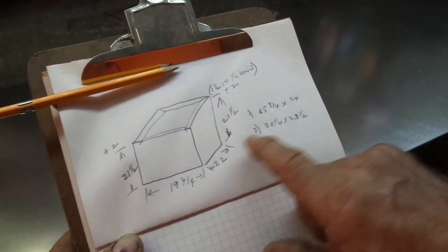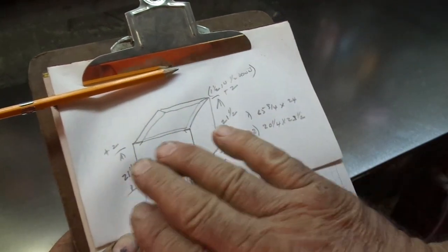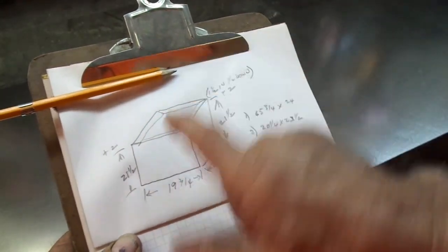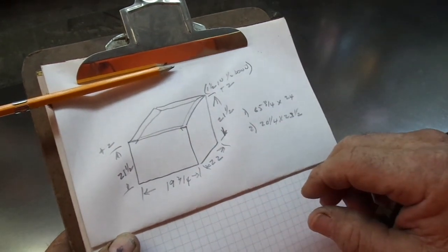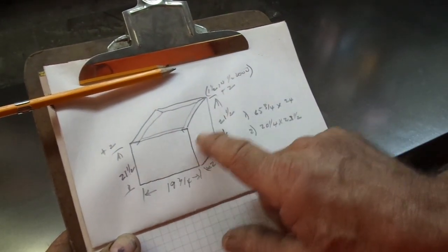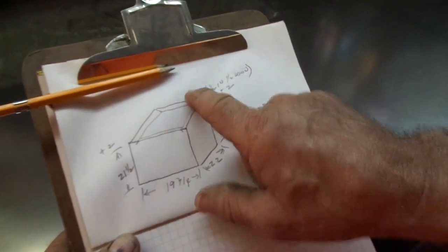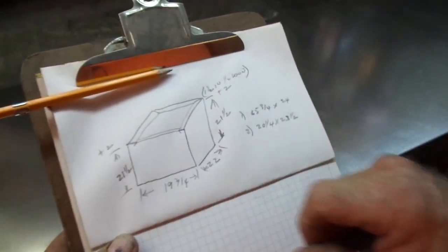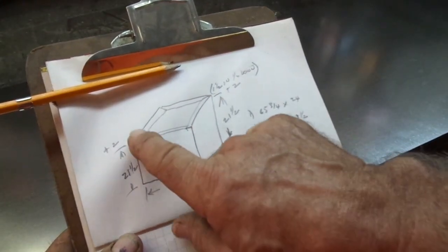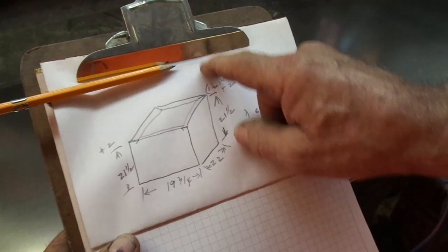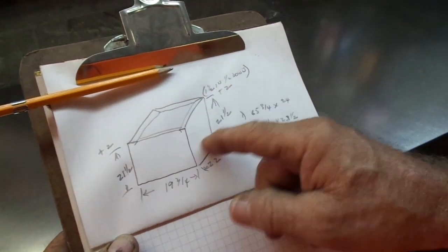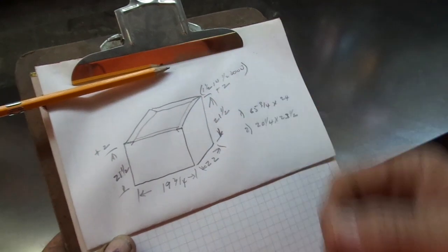We will end up with a U-shaped wrapper with a hole in each end or side. So then we take the 19.75 dimension, and because there's going to be a Pittsburgh on this and on this, we'll have a quarter inch bend on the 19.75 on both sides and the bottom. So our cut size is going to be 20 and one quarter by 23 and a half for the two ends or the sides that plug into the horseshoe-shaped wrapper.